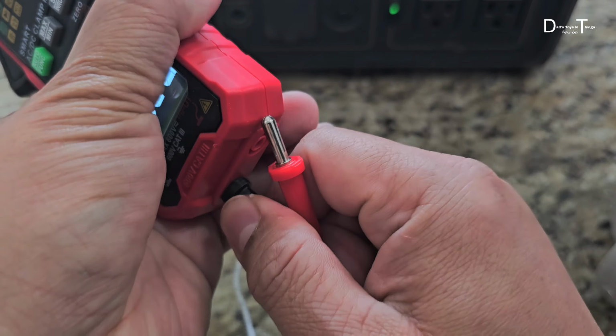So it's in auto. What I'm going to do is go from here — see if I can get that in there, this thing's a little tight — 122.6. From AC, I'm going to switch without touching anything. This is still in auto. I'm going to cut power to the grid and test the voltage on the battery, again without changing anything on the meter.